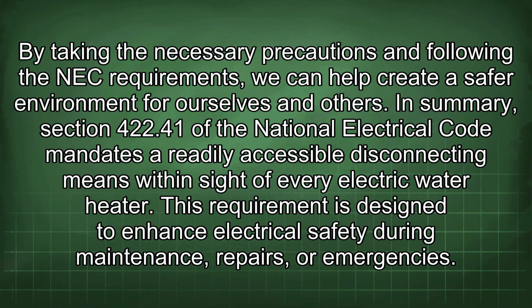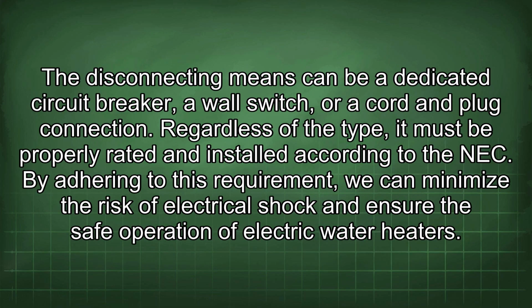In summary, Section 422.41 of the National Electrical Code mandates a readily accessible disconnecting means within sight of every electric water heater. This requirement is designed to enhance electrical safety during maintenance, repairs, or emergencies. The disconnecting means can be a dedicated circuit breaker, a wall switch, or a cord and plug connection. Regardless of the type, it must be properly rated and installed according to the NEC.